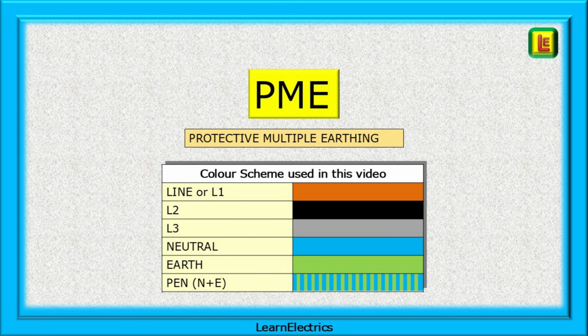We can take a look at PME systems now, protective multiple earthing, multiples or many protective earthing points. The following drawings are all coloured, and the colour scheme that I've used for these is as shown in the chart. The harmonised colours are brown, black and grey for the phases, with blue for neutral. For earth, I've chosen to use a solid green as it's easier to see on some drawings, and I don't want it confused with the PEN conductor, which is coloured blue and green.